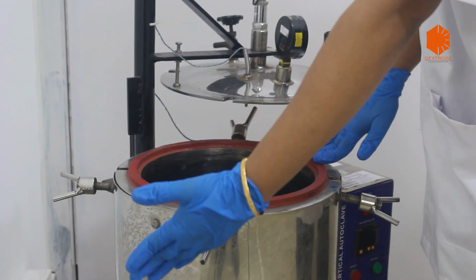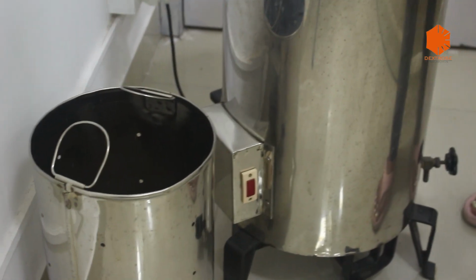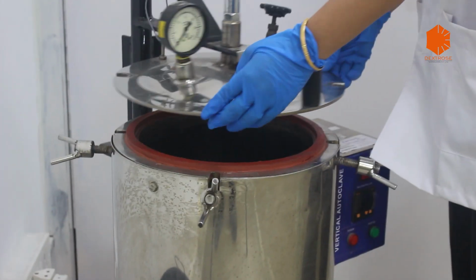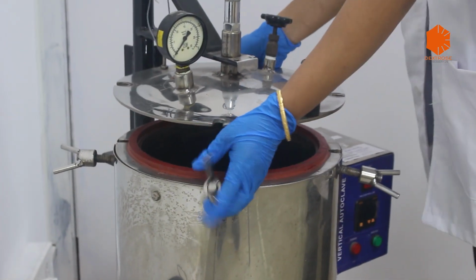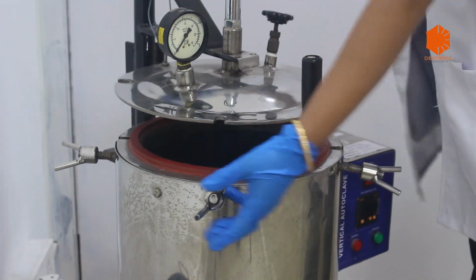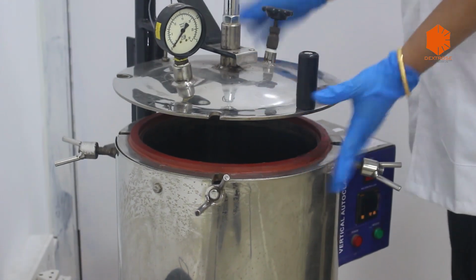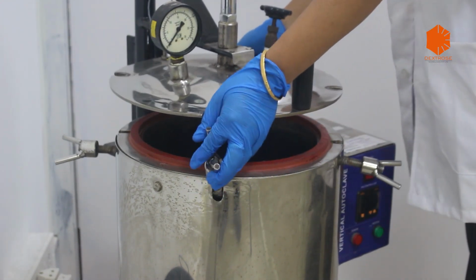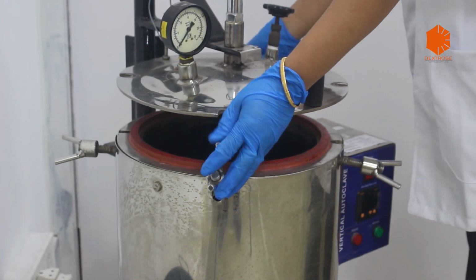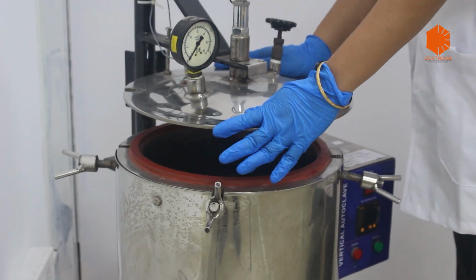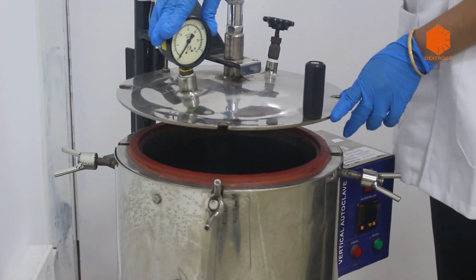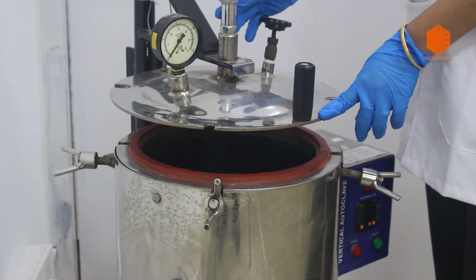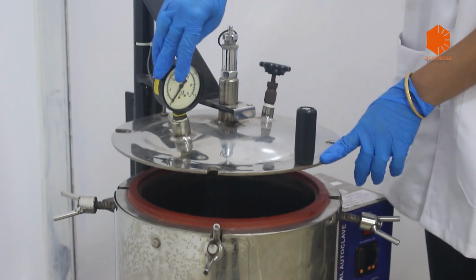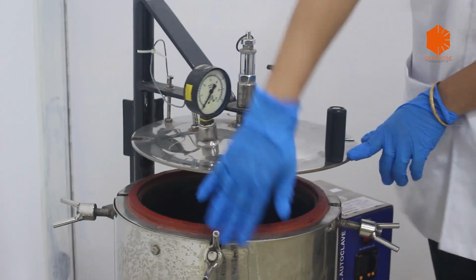Okay, and then you will place all the components to be sterilized, place the basket here and close the lid with the help of these screws which you can see on all the four sides. Just ensure that you operate the opposite facing screws at the same time to ensure proper closing of the lid. So on the lid is a pressure gauge, a safety valve and a whistle. So pressure gauge indicates the pressure built up in the autoclave.